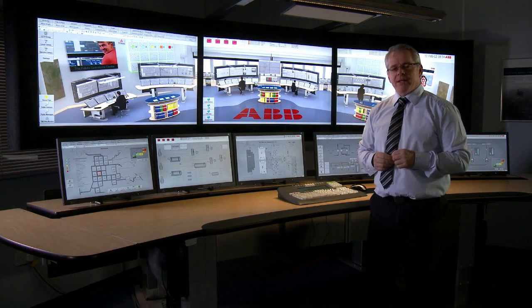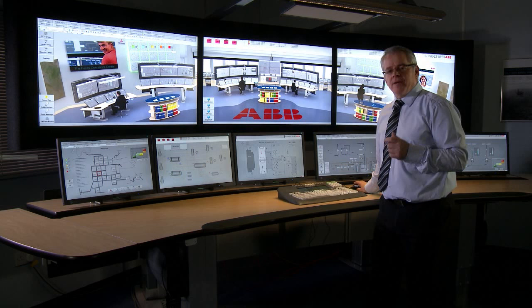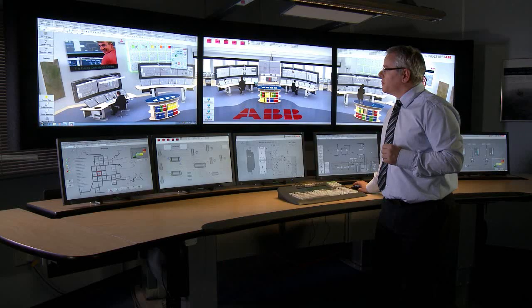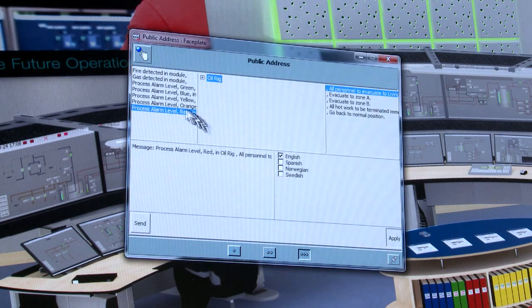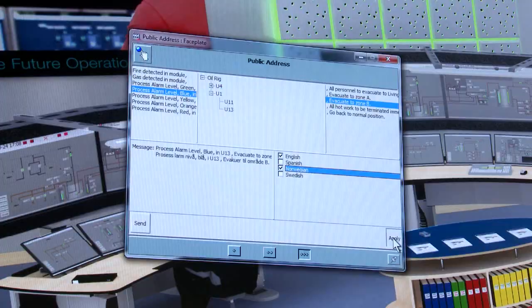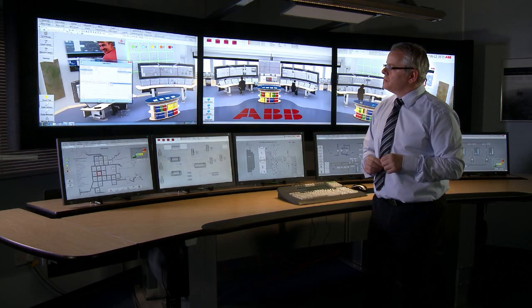As part of the telecoms integration, 800XA also allows us to integrate the public address and general alarm systems. This is extremely important when we've got large production plants with multiple nationalities dispersed throughout the plant. The 800XA system can pick up any system alarm — in this case we're going to generate a fire alarm — and once the alarm is generated, the message is automatically inserted into a faceplate displaying a particular message that needs to be transmitted throughout the production plant. This is a true text-to-speech system where we can change the message if needed, and we can select different languages and transmit that right across the production plant or certain areas of it. For example: 'Process alarm level blue in U13.